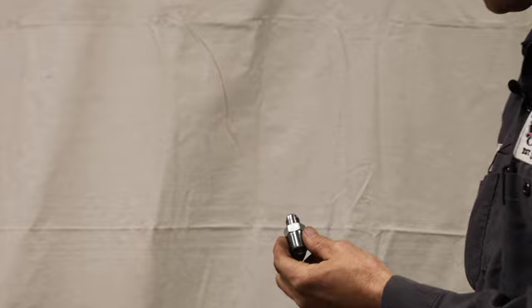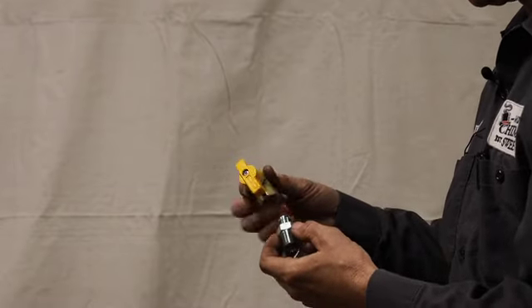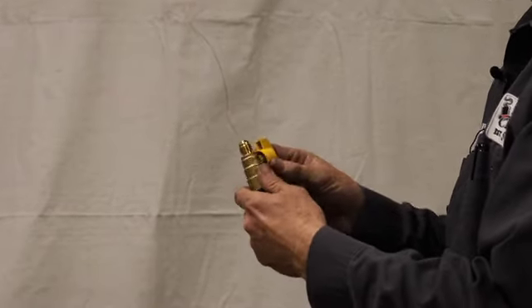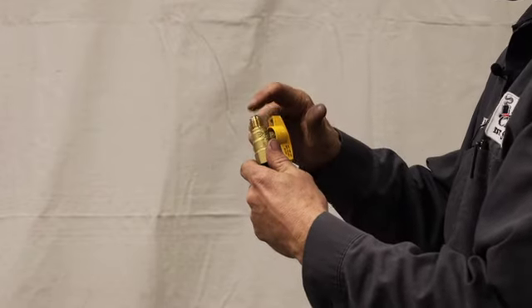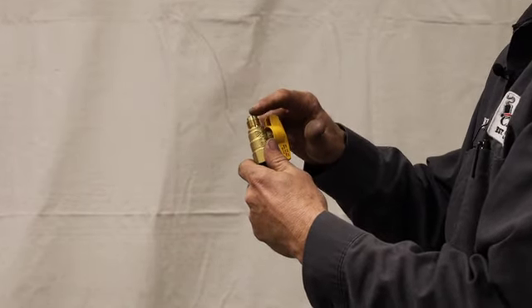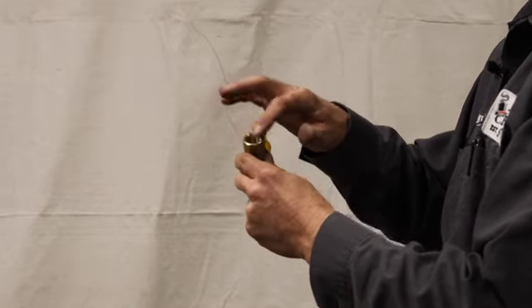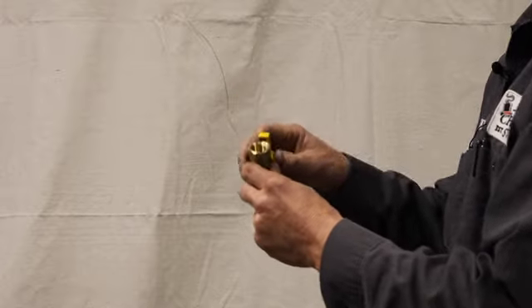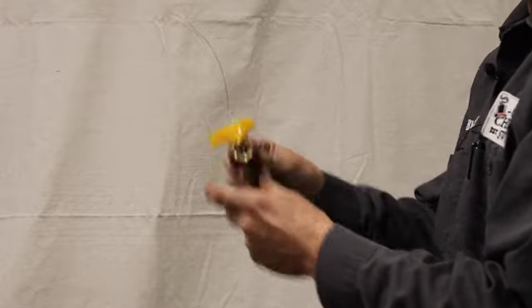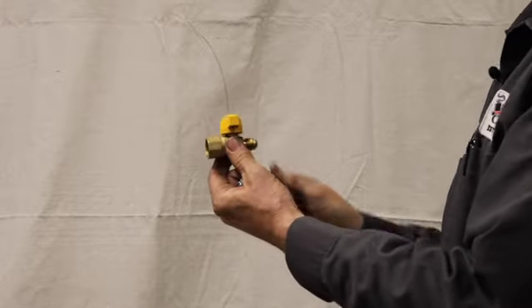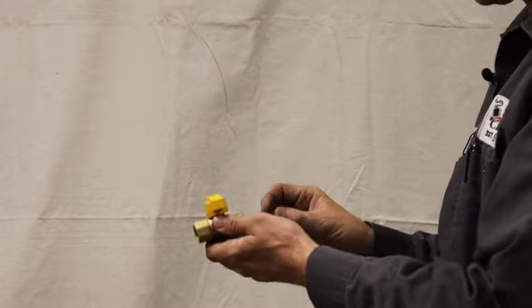Very important, we've had several gas leaks in different places, and it's because of rookie mistakes. Again, we have a flared fitting for compression, no sealant. And then on this side, we have iron pipe. Yes, we use sealant there. And this is just a standard stopcock, what you see sticking out the wall when you go to attach your gas flex line.